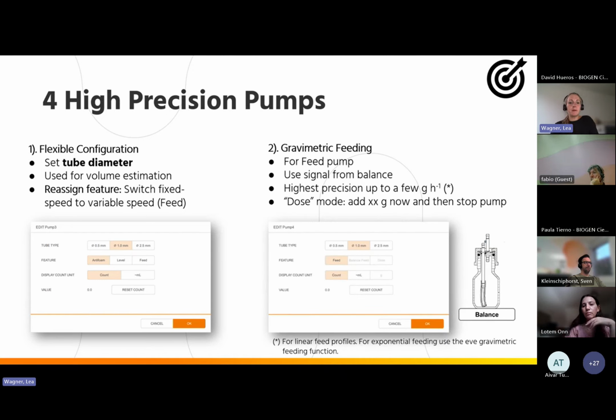Moreover, the 4th pump, so the feed pump, can be changed to gravimetric feeding if the customer buys a balance and connects the balance to Minifors 2. And then not only milliliter or milliliter per minute can be chosen as unit, but also grams per hour, which is a little more accurate. And there's also a dose mode available, which means that the customer can add, for example, 100 grams of glucose and then stop pumping. So a one shot of feeding. And in case the customer would like to have more complex feeding strategies, for example exponential feeding, then these strategies can be used when having Eve. So then the customer can also use more complex feeding strategies, maybe also for a continuous culture.